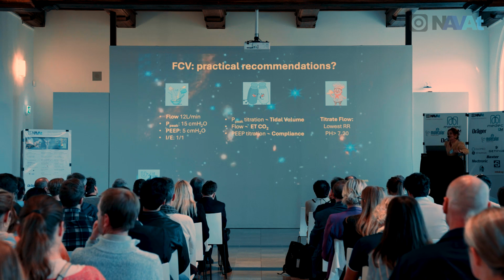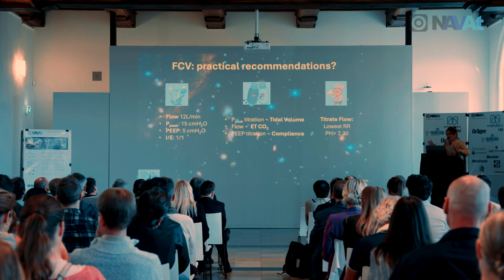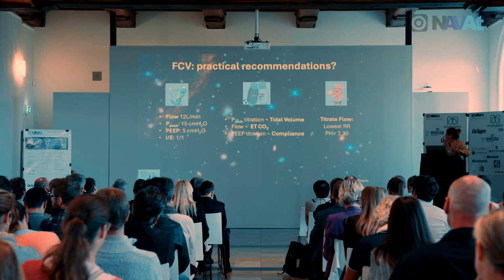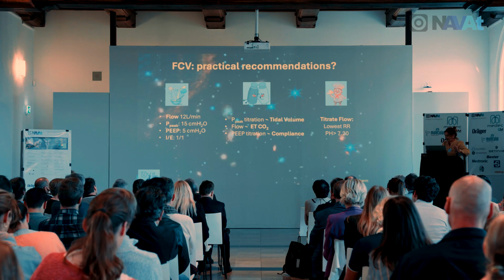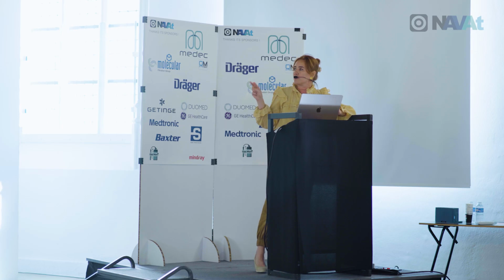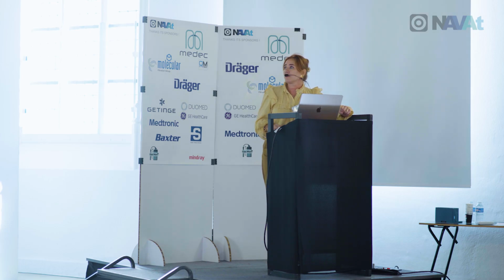So very important is that it is a totally different way of thinking and using a ventilator. You're not setting your respiratory rate and your tidal volume; those two parameters are dependent upon the flow rate, the peak, and the PEEP of your patient. We can even apply flow-controlled ventilation during one-lung ventilation, just with the same settings as I just mentioned.